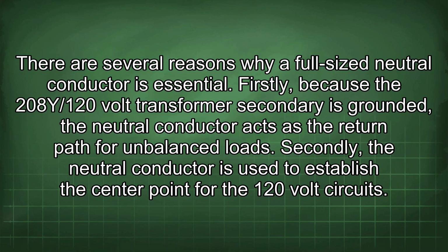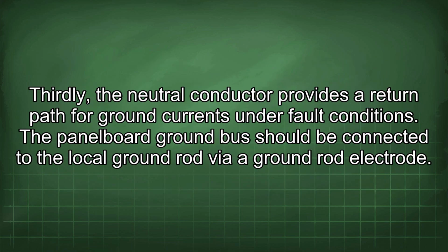There are several reasons why a full-sized neutral conductor is essential. Firstly, because the 208Y/120-volt transformer secondary is grounded, the neutral conductor acts as the return path for unbalanced loads. Secondly, the neutral conductor is used to establish the center point for the 120-volt circuits. Thirdly, the neutral conductor provides a return path for ground currents under fault conditions. The panelboard ground bus should be connected to the local ground rod via a ground rod electrode.